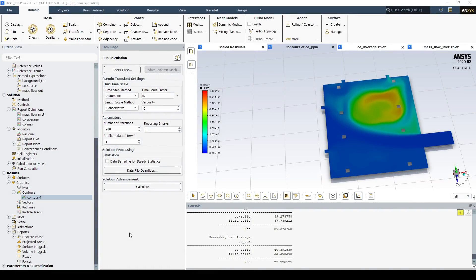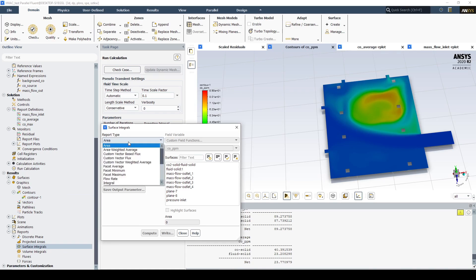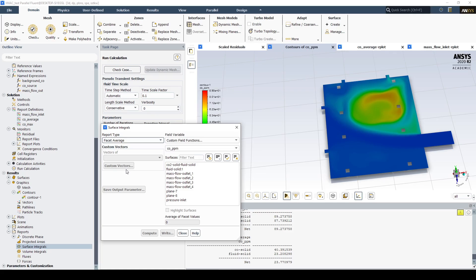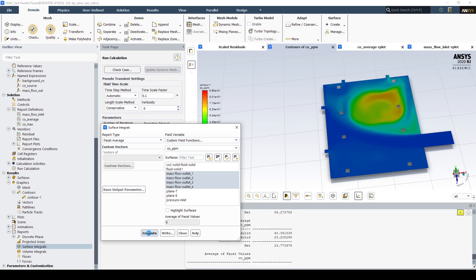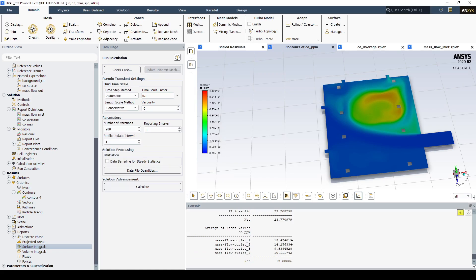We can investigate how much CO actually passes through the outlets. Going into surface integrals and reporting a facet average to see how much CO is passing through the outlets, we compute it and can see that outlet one — which is up here — is removing the most amount of CO, and it decreases as we go around the outlets.